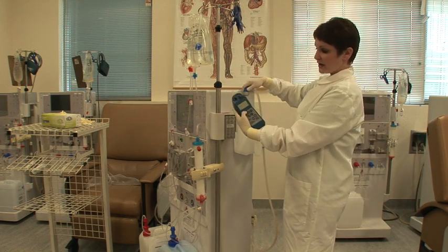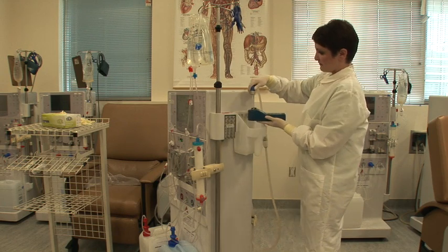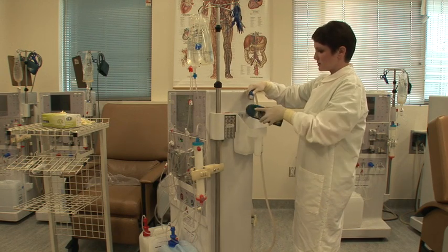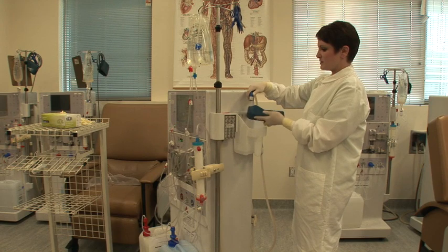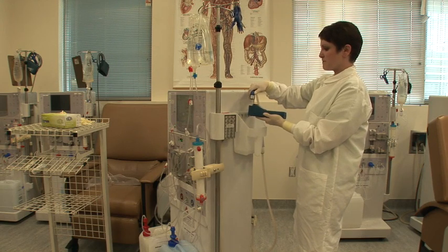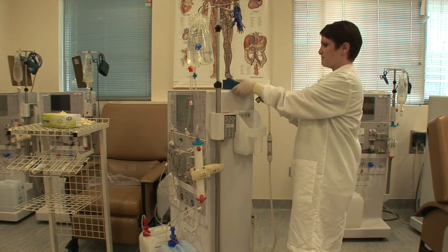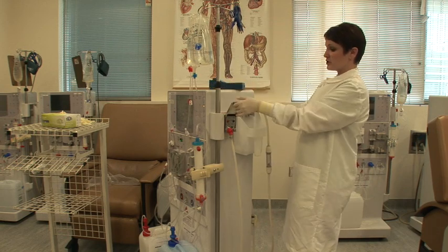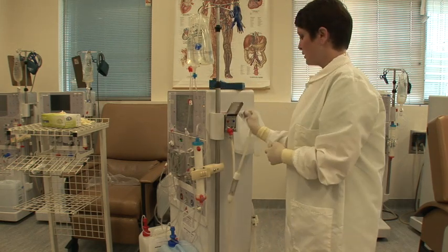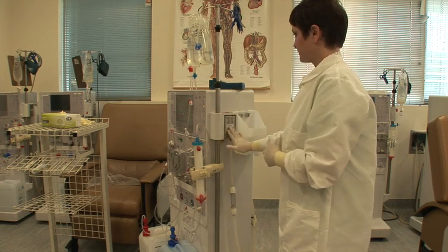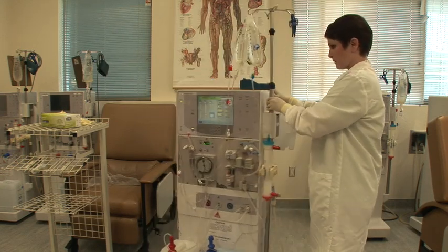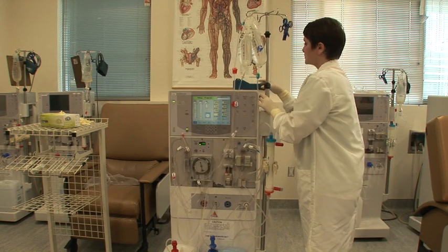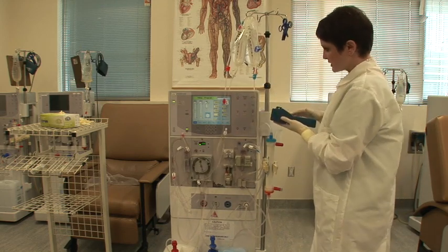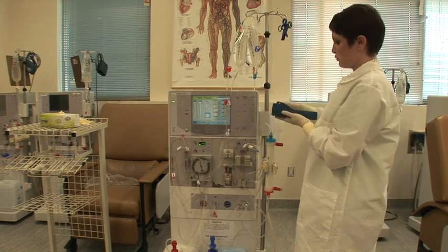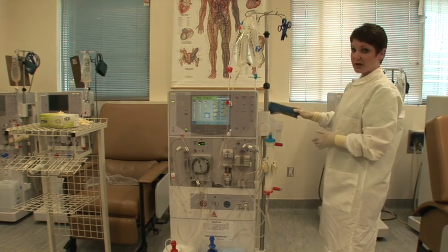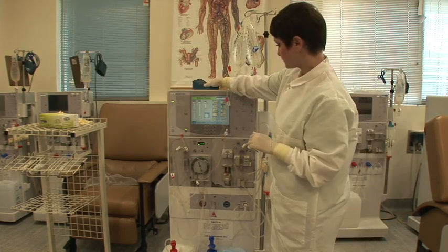Hit the conductivity button on your Myron L and fill it up once, twice, third time's a charm. Set your Myron L up. Open the door, that will stop your fluid flow, and replace your Hansen connector. So then you're going to verify that my conductivity is 13.2 and 13.0. You can dump that in your priming bucket. You're done with your Myron L.